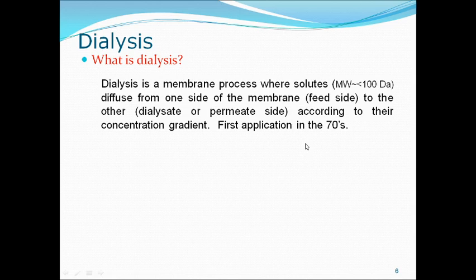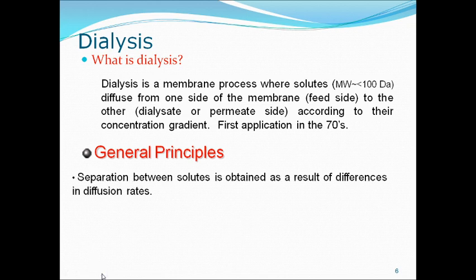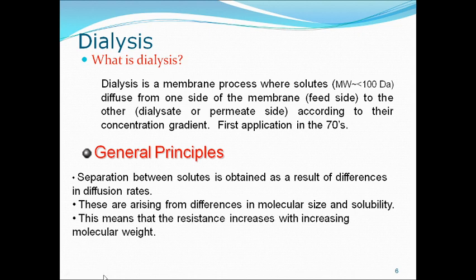The first application of dialysis came into picture in the 1970s; after that, a lot of advancement has occurred. Still people are working efficiently, and there is scope for you to improve the dialysis machine. Dialysis machines nowadays are available for lakhs of rupees — you can reduce the cost. If you are able to reduce the cost even by 10,000, that is an achievement. The general principle: separation between solutes is obtained as a result of differences in diffusion rates arising from differences in molecular size and solubility. Resistance increases with increasing molecular weight — if molecular weight is high, it will not diffuse because the membrane becomes a limiting factor.